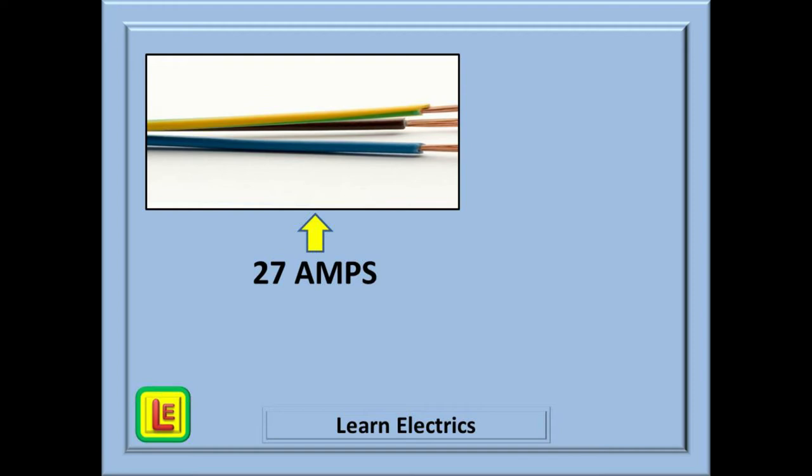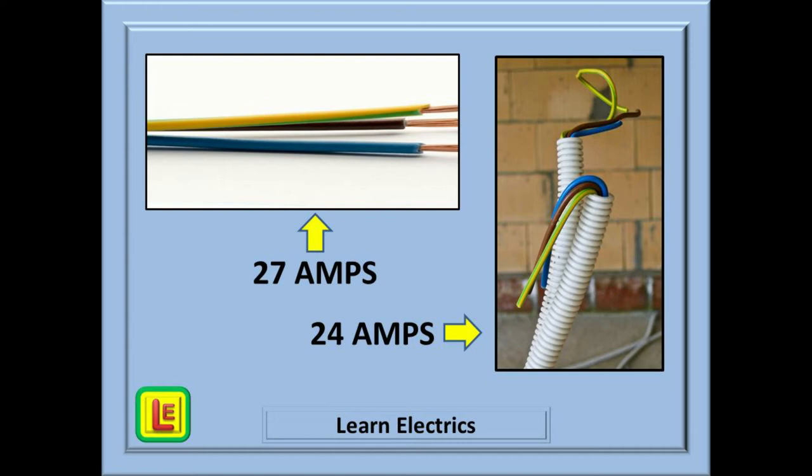This slide shows 2.5mm PVC singles installed in a ducting system with lots of space and free air, where it is easy to lose heat and they may not reach the limiting temperature of 70 degrees centigrade until 27 amps or more passes through them. But if they are installed in plastic conduit, as shown here, we may need to reduce the current to 24 amps or less to prevent overheating. If we absolutely needed the full 27 amps because the machine they are connected to draws close to 27 amps, then we have a problem. Fortunately, the tables will tell us to what size we must increase the cable to stay within our temperature limits.